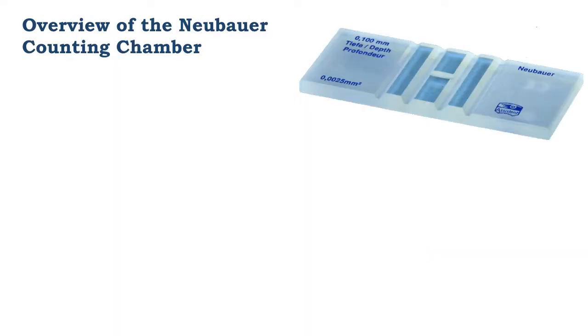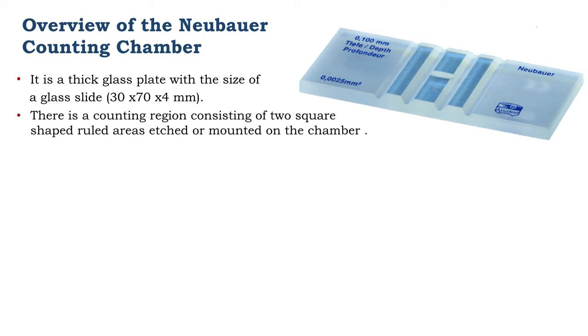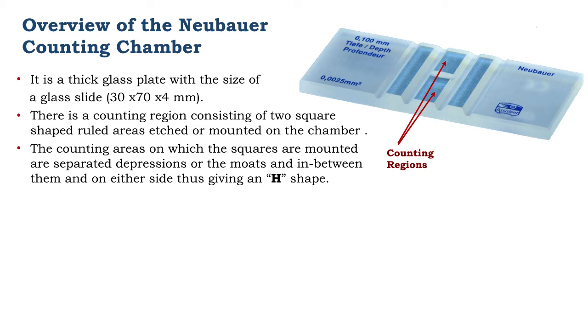Now let's have an overview of the Neubauer counting chamber, especially the counting surfaces. The Neubauer counting chamber is about the size of a glass slide, just a little thicker. It has counting surfaces etched or mounted on the surface — there are two — and they consist of square ruled areas. The two counting surfaces are separated by depressions or moats in between them and on either side, giving them a characteristic H shape.